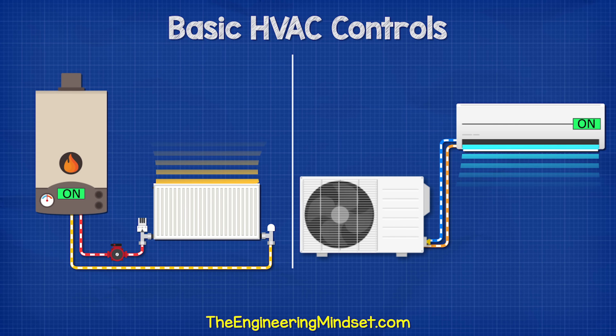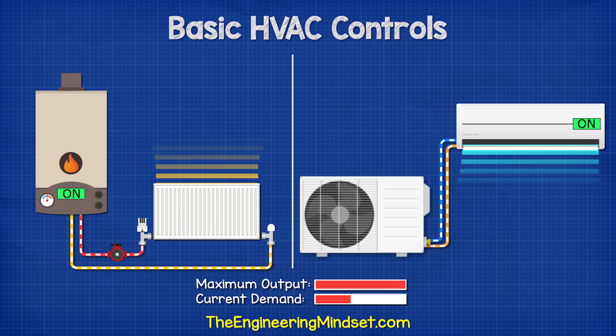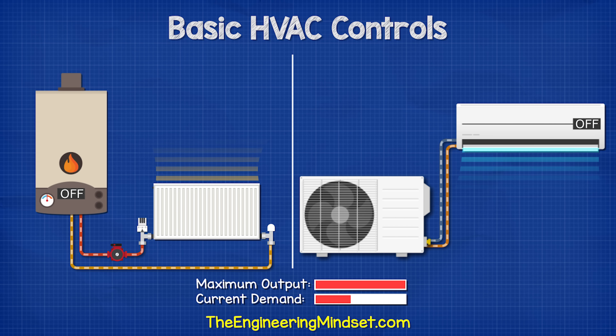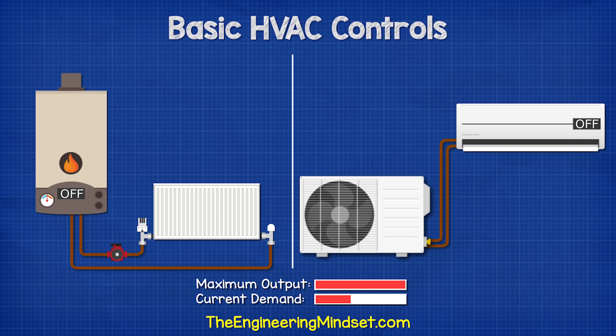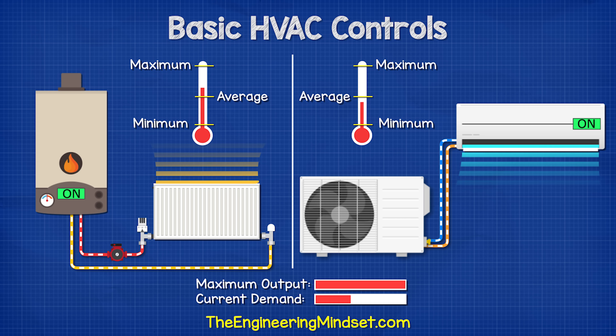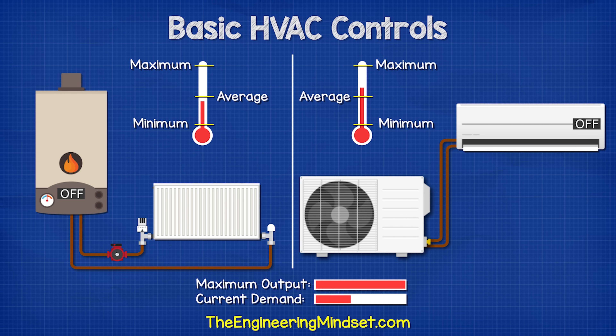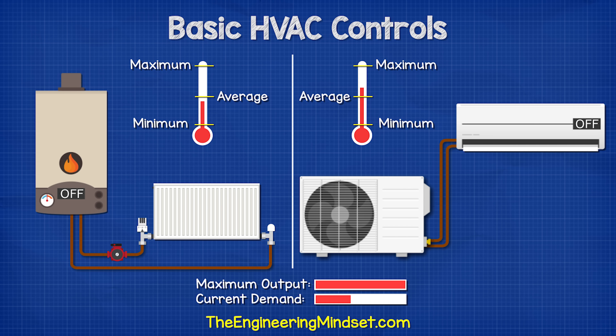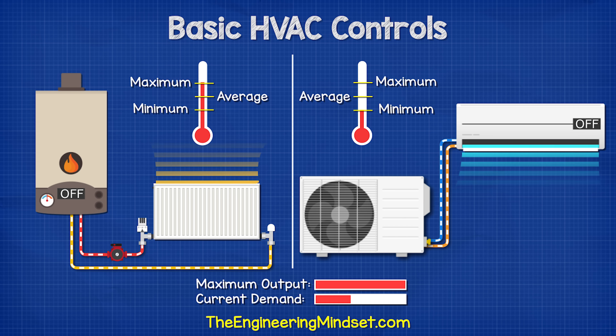We could also control a heating or cooling system with a simple on-off control. For example, if the heating or cooling demand for a room is only half of what the system can provide, then we could just turn the system on for half of the time and off for the other half, perhaps every 30 minutes. This would work, but not very well, because it results in the room being too hot and then too cold, although the average temperature appears normal. To improve this, we could divide this into smaller time intervals, which would achieve a more even temperature.